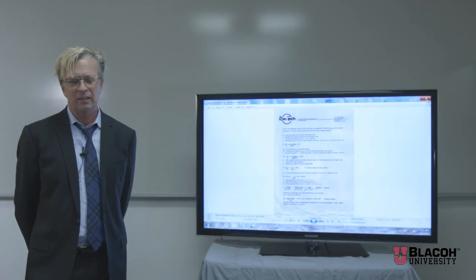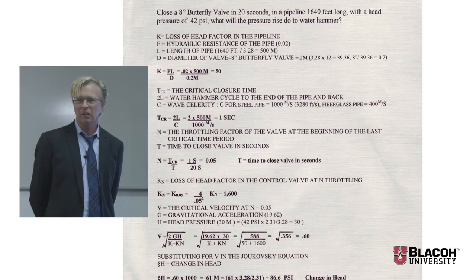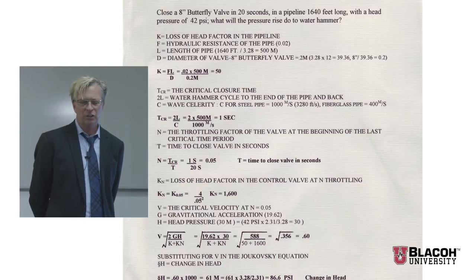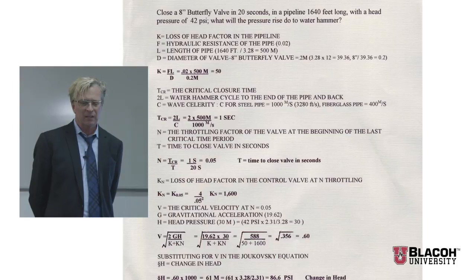When we look at doing hydraulic modeling and surge analysis, I usually take a look at your basic math. In this case we're breaking down the math, looking at an 8-inch valve closed in 20 seconds and examining the cause and effect of the surge that was created in that 20-second closure.